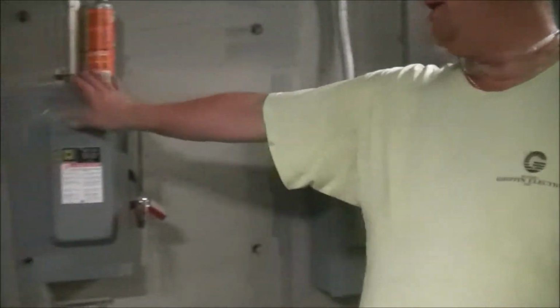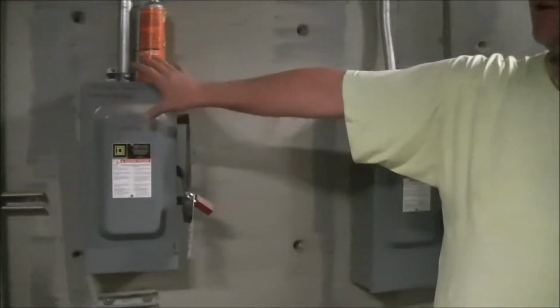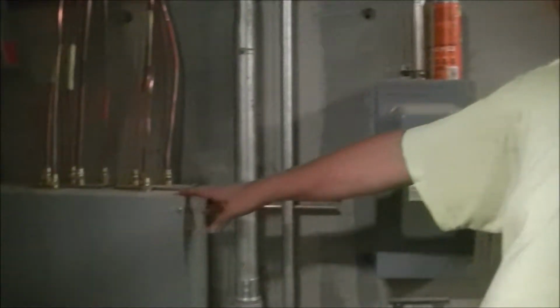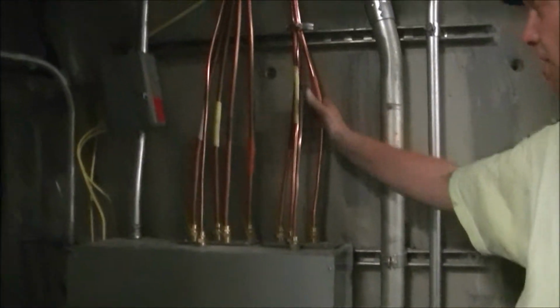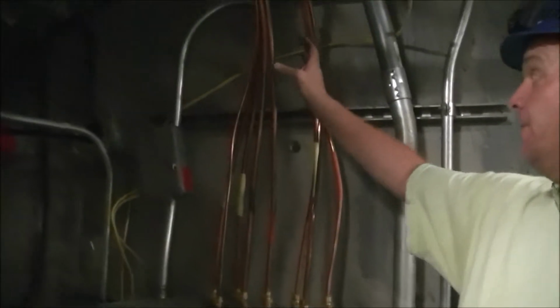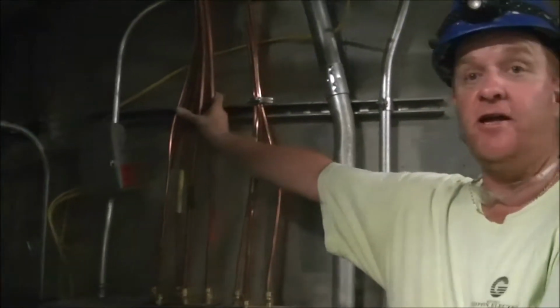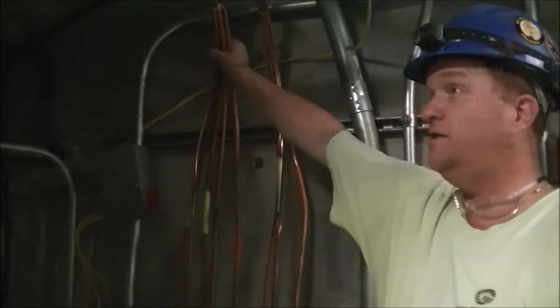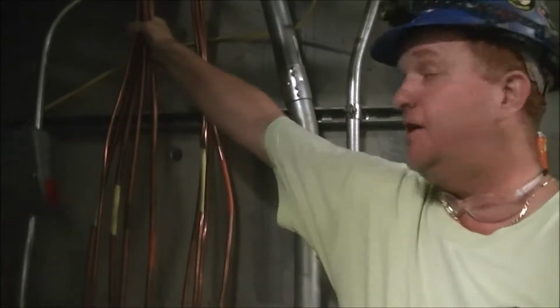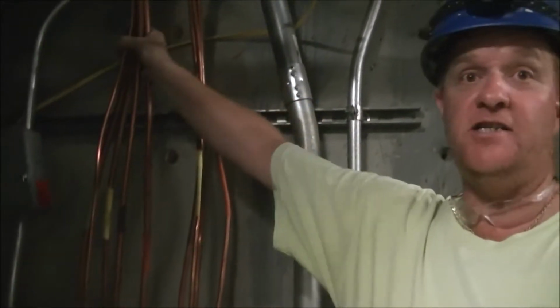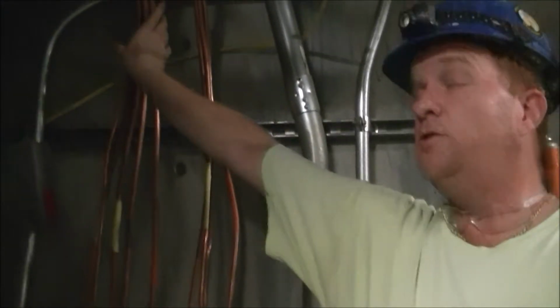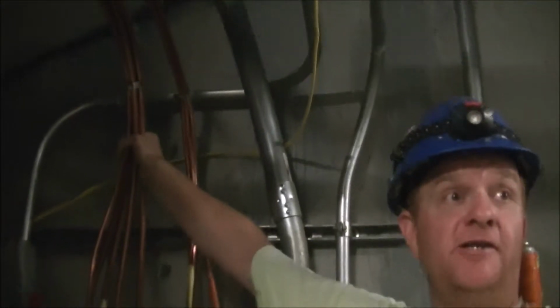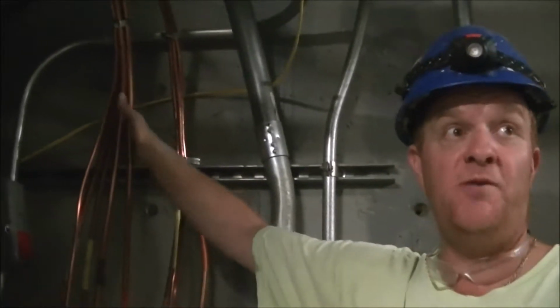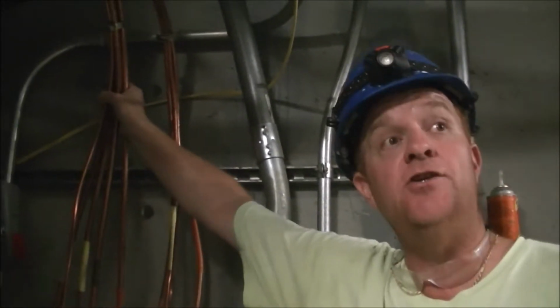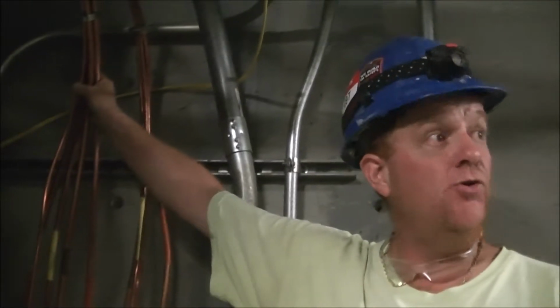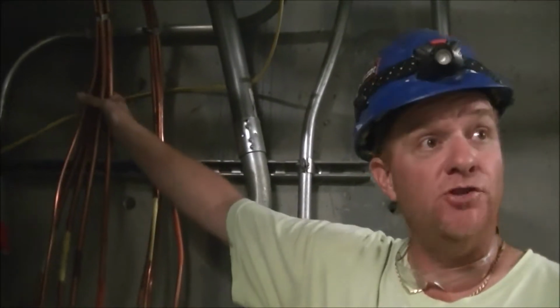Switches on the wall, these are redundant. We're going to mark them up that they are spares. This little setup that we've got in the corner at the moment feeds out to the generator. So basically this set of wires here, MICC cable, these feed the ATS switches. We use this kind of cable because it's 2-hour fire rated. It's full of powder, when the powder gets to a certain temperature, it turns to ceramic, which then protects the core inside it, so that's what makes it last for 2 hours.